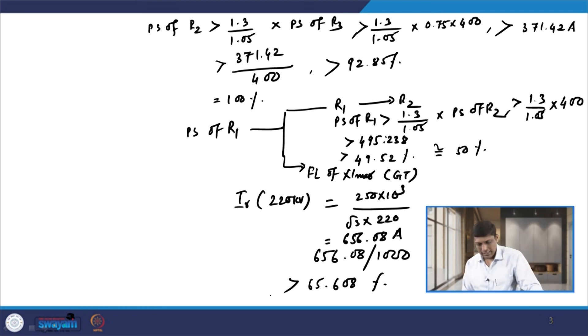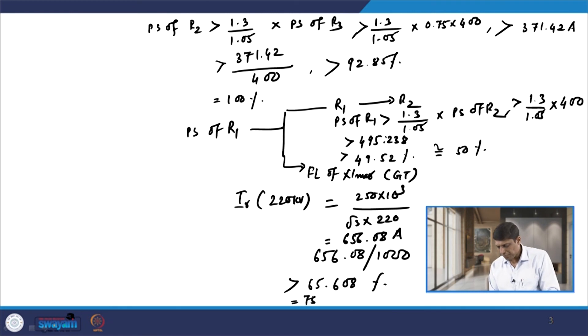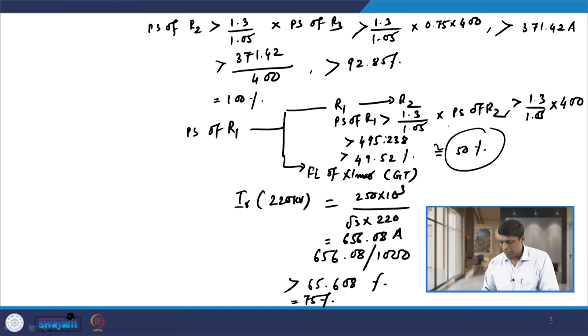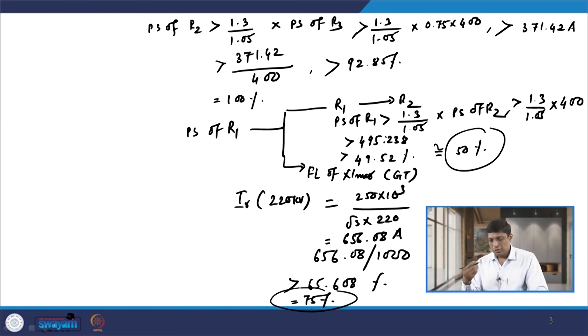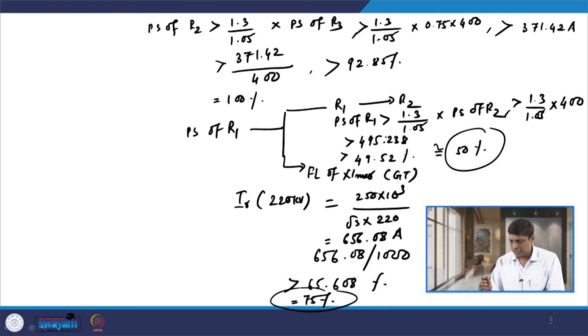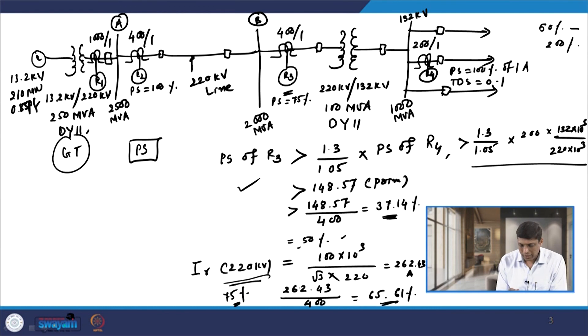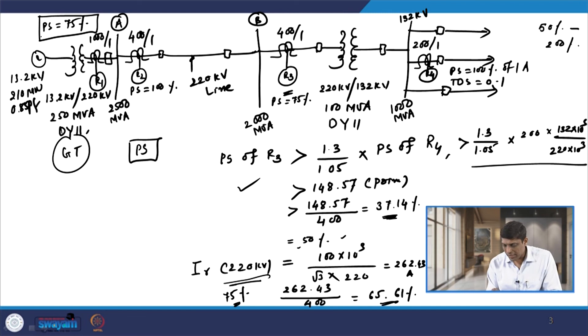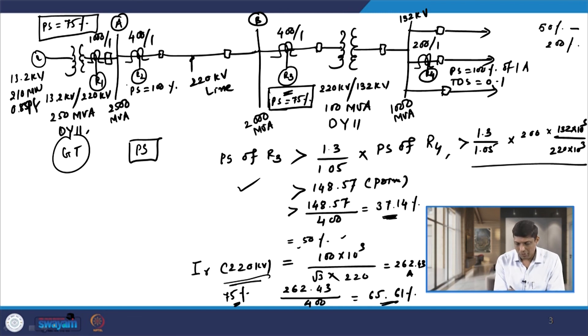Since we obtain 50 percent from one rule and 75 percent from the transformer rated current check, we select the higher value — plug setting of relay R1 is 75 percent. We have now decided the plug settings of R1, R2, and R3.